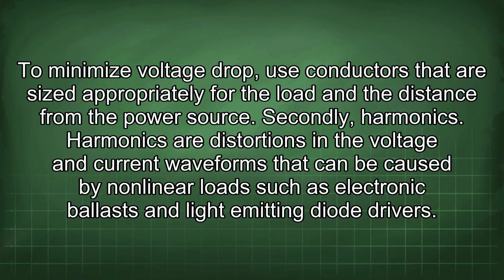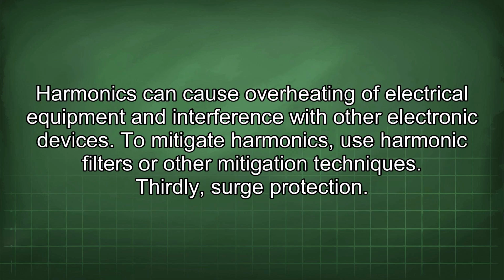Secondly, harmonics. Harmonics are distortions in the voltage and current waveforms that can be caused by nonlinear loads such as electronic ballasts and light-emitting diode drivers. Harmonics can cause overheating of electrical equipment and interference with other electronic devices. To mitigate harmonics, use harmonic filters or other mitigation techniques.